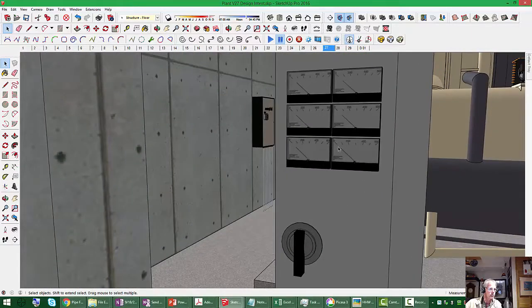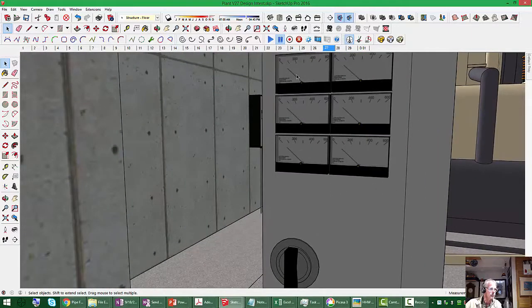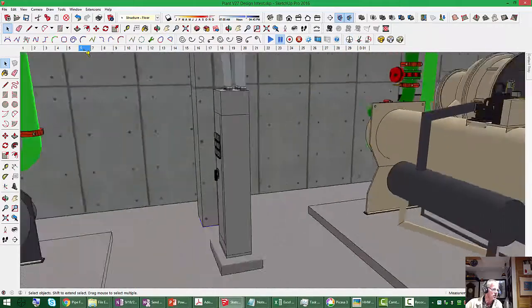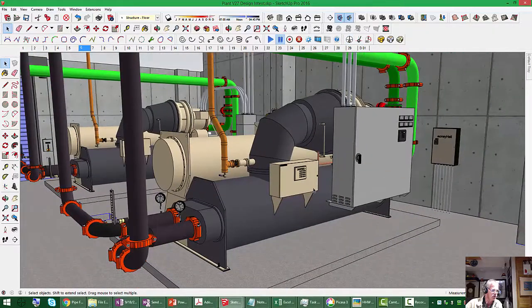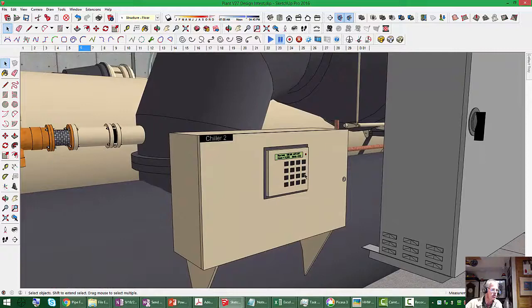If we go over and look at its starter, we discover there's no volts, no amps. The starter is disengaged. Okay, so that machine isn't running. And if you're there in the field, it wouldn't be making noise either. That'd be kind of another clue. If we go look at the second machine, use the same technique.